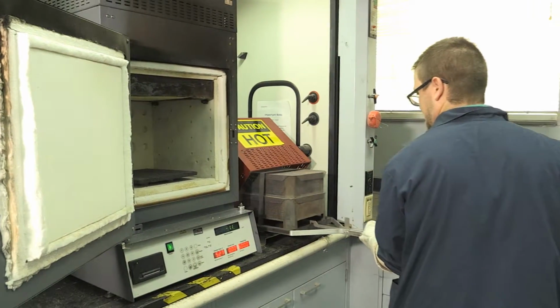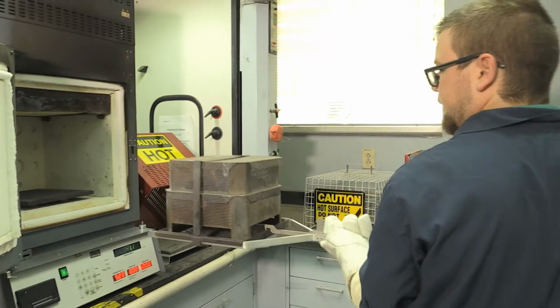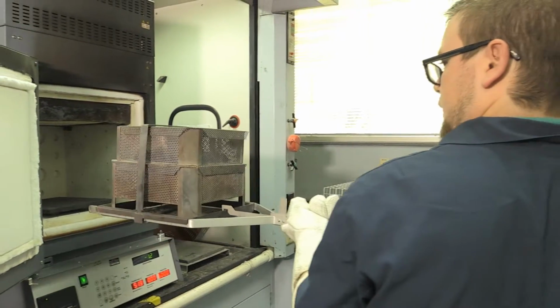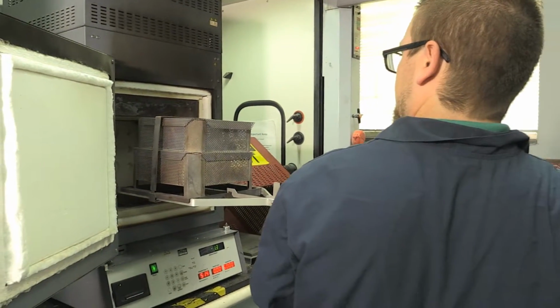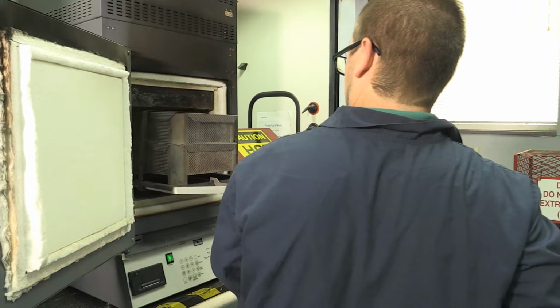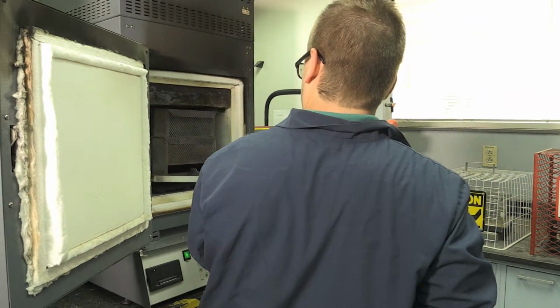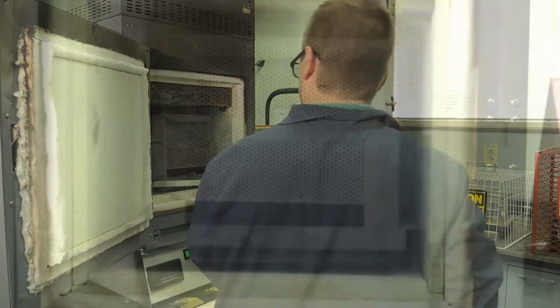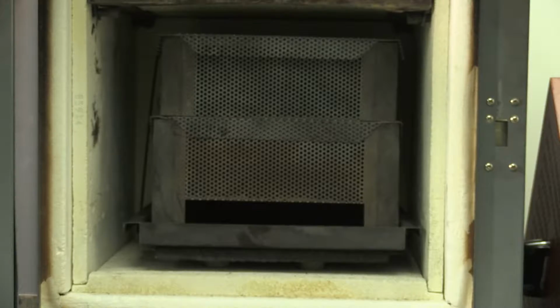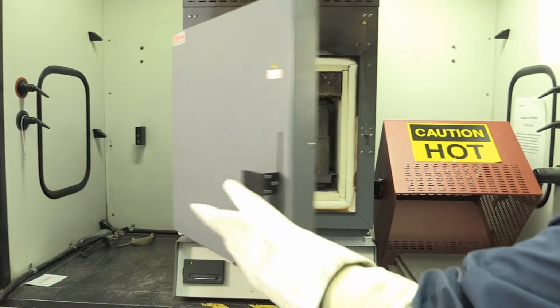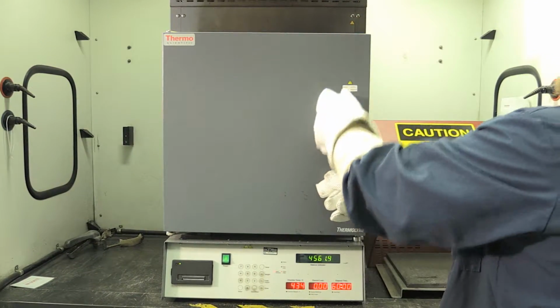Use the basket lift to insert the sample into the ignition oven. Ensure that the basket does not move the base plate off of the scale. Also, ensure that the basket does not touch the wall of the oven. Close the oven door and begin the ignition test.